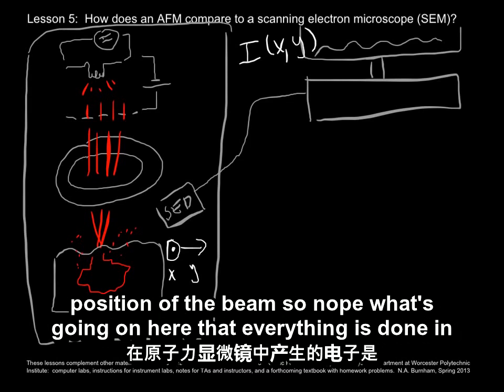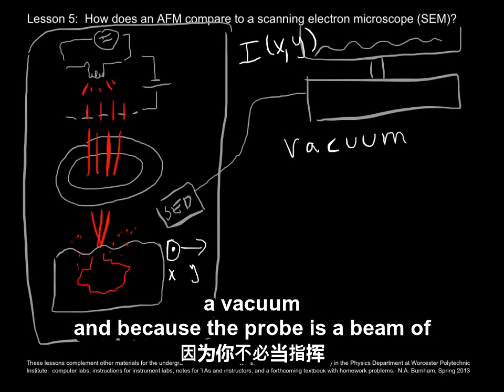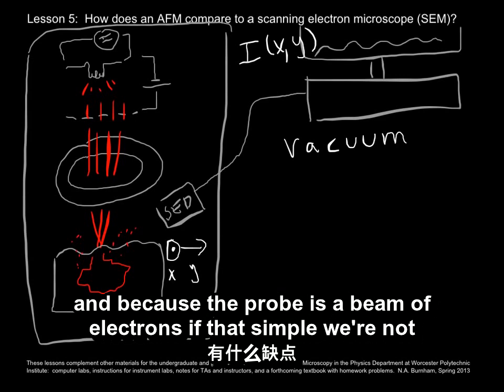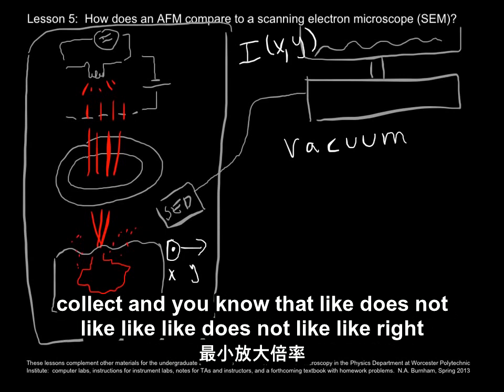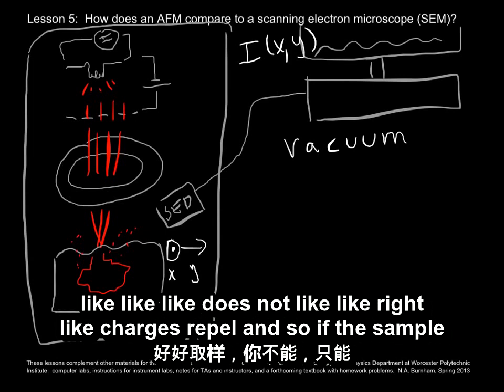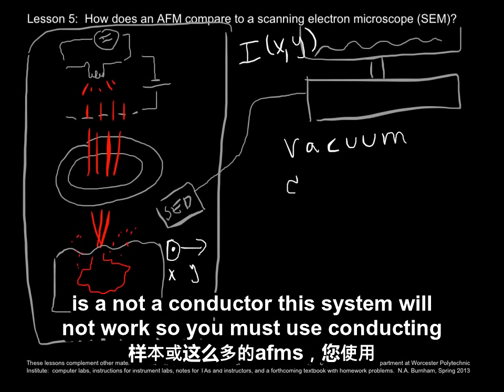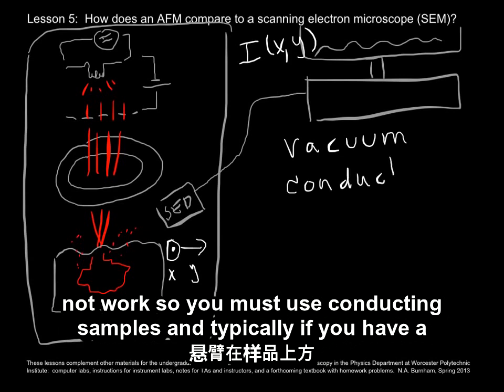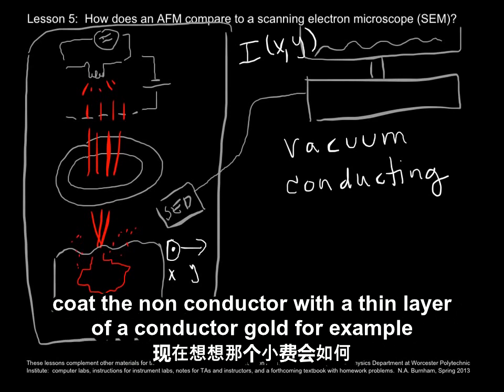Note that everything is done in a vacuum, and because the probe is a beam of electrons, if the sample were not conducting, all the electrons would collect. Like charges repel, so if the sample is not a conductor, this system will not work — you must use conducting samples. Typically, if you have a non-conductor, you coat it with a thin layer of a conductor such as gold.